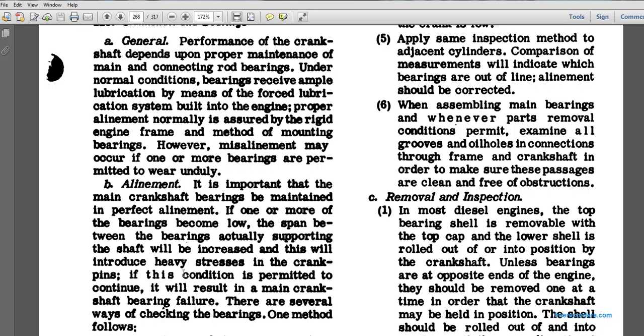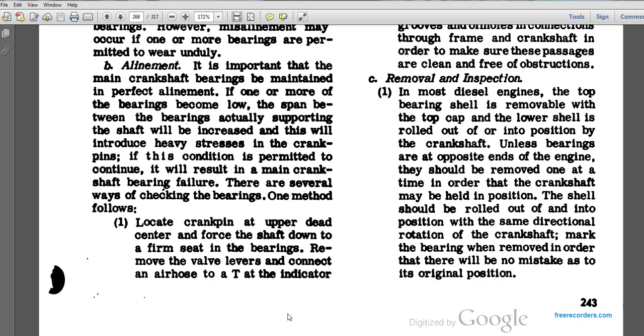It is important that the main crankshaft bearings are maintained in perfect alignment. If one or more of the bearings becomes low, the span between the bearings actually supporting the shaft will be increased, and this will introduce heavy stress in the crank pins. This condition must not be permitted to continue, or it will result in main crankshaft bearing failure. There are several ways of checking the bearings. One method is to locate the crank pin at upper dead center and force the shaft down to a firm seat in the bearings.